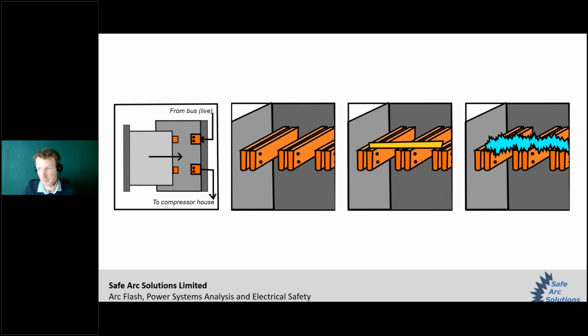The metal piece is probably flung clear at this point by the forces involved, but the high fault current continues to flow. It had ionized the air between the conductors and is using this as a conducting route. There's nothing to constrain this arc which forms, and it gives off a huge amount of heat, releasing huge amounts of thermal energy, which basically vaporizes anything close by, metalwork, copperwork, parts of the switchboard, and starts producing toxic fumes and a rapidly expanding series of gases. The pressure is going to force that breaker forwards towards the electricians, and that allows this cloud of heat and vapors to be released into the switch room, engulfing them.